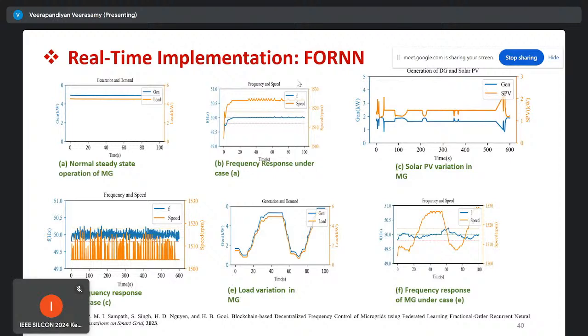The frequency of the system is maintained tightly whenever there is PV injection into the system. The orange line shows the PV injections, and this is the synchronous generator's response to mitigate the frequency overshoot or undershoot in the system, thereby maintaining the system frequency.